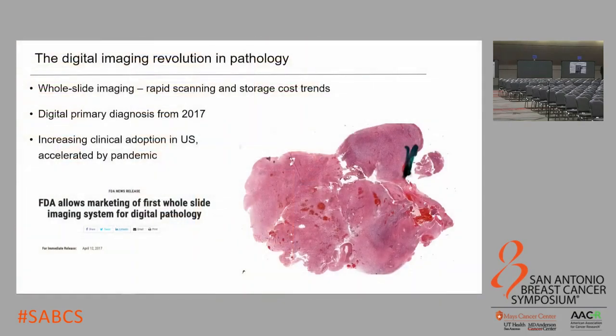The abstracts we'll be discussing today deal with a technology called whole slide imaging. Whole slide imaging is a microscopic approach to generate high magnification images of entire tissue sections. What's really led to growth in this technology are improvements in speed. Today's scanners can generate a 40x objective image in approximately 90 seconds for a single slide.